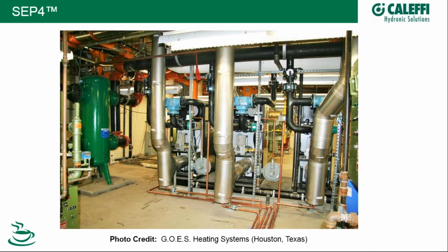So here is a job of a SEP4 from Texas. It's over here on the left-hand side, sitting pretty. And connected to it are several boilers. You can see 3 of them here. There's 2 or 3 off to the right, but the photograph couldn't get them in. So they're all feeding into a supply header that drops down and goes into the top of the hydraulic separator, delivering the heat, then journeying back to the return headers, and on the return back to all of these boilers.